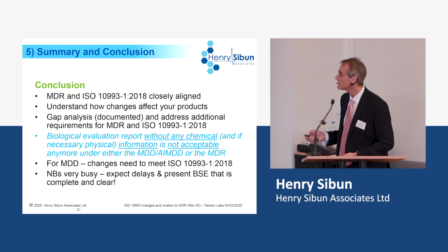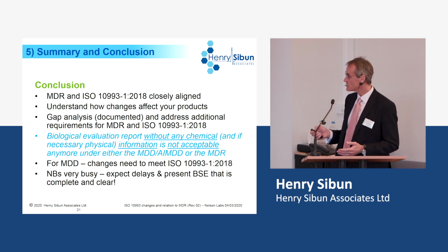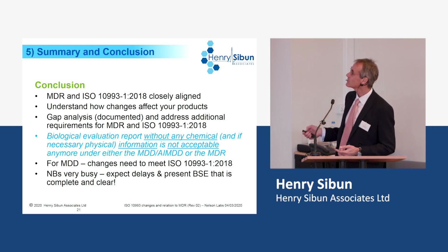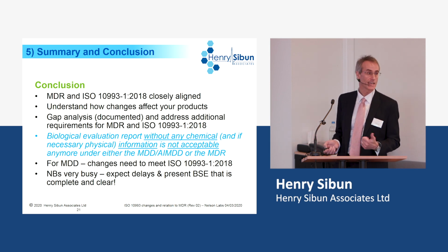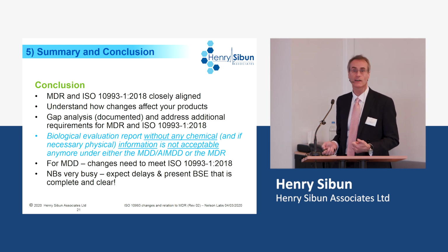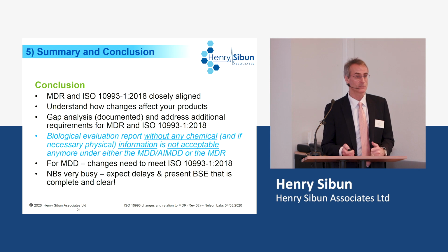And lastly, if you've got a biological evaluation, even under the MDD, that does not consider chemical and physical characterization, this will not be accepted under the MDD or the MDR or the AIMDD. Okay, you need to have that information. It's been a requirement for many, many years. It's not new. It was just never enforced.